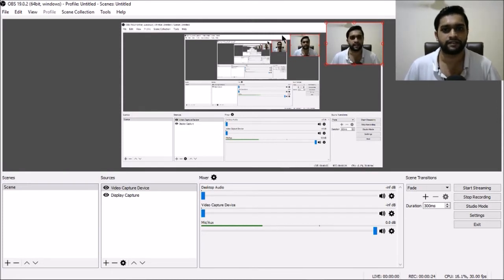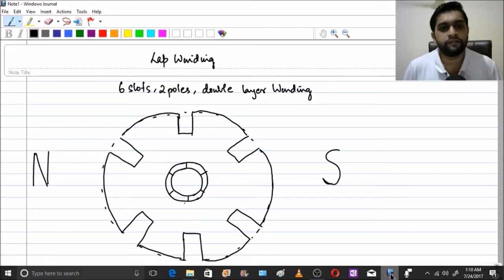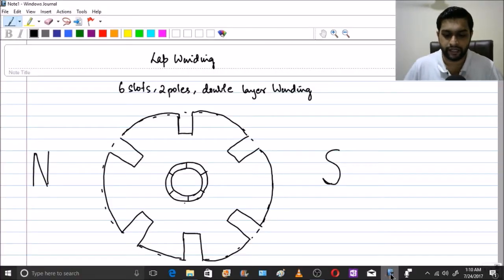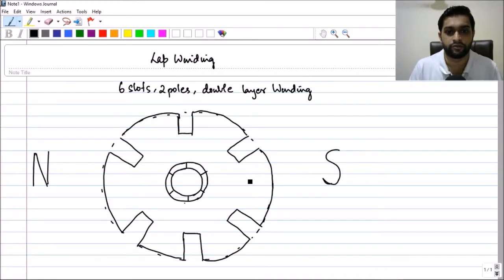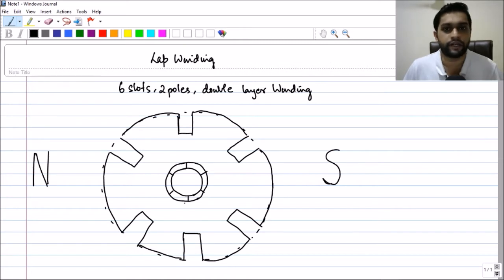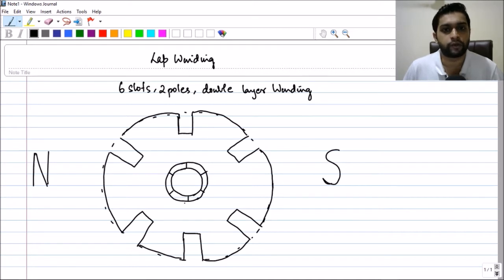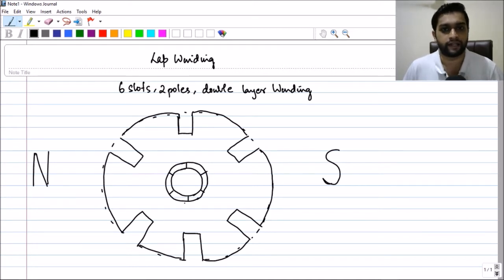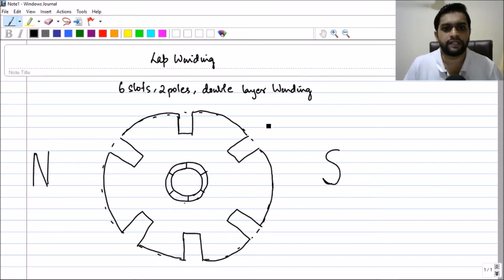So let us start. Here we have our six-slot machine. Clearly you can see there are six slots: one, two, three, four, five, six. Because there are six slots and for each slot you are having one commutator, you have one commutator per slot. It's a double layer winding with six slots, so each slot will have two conductors, giving a total of 12 conductors.